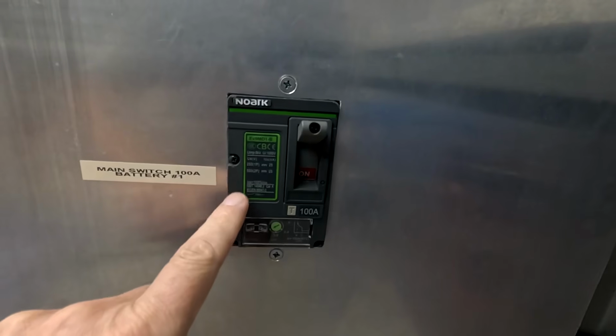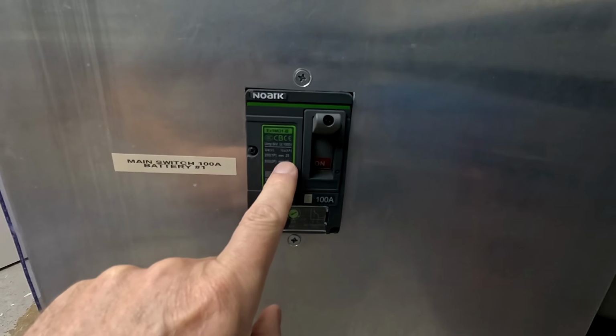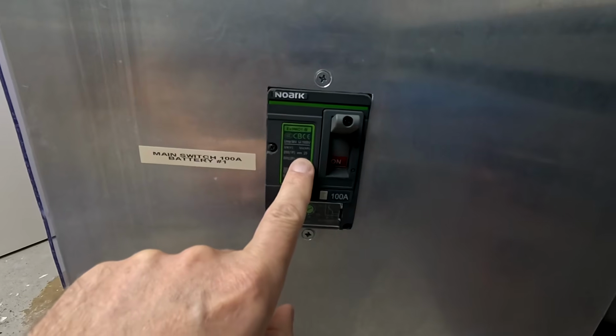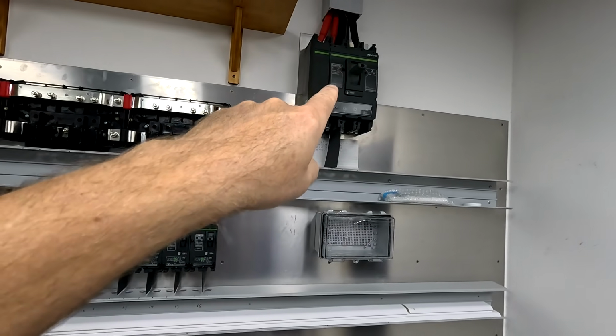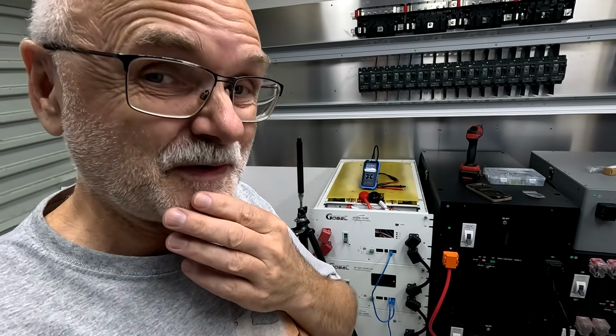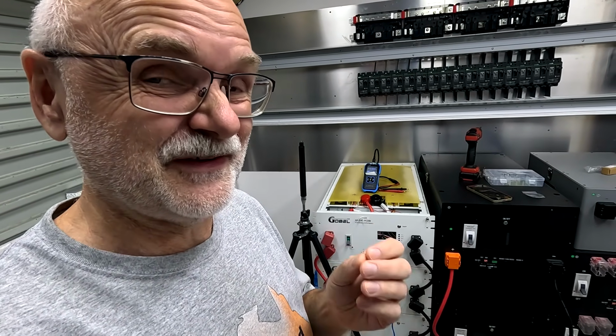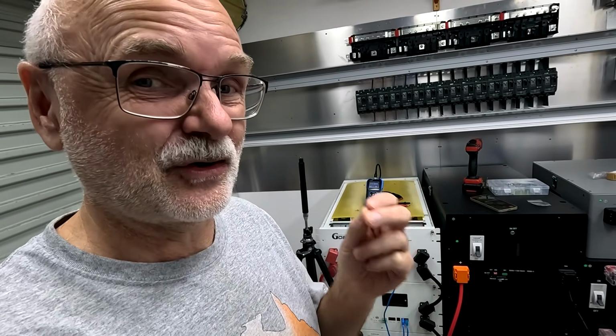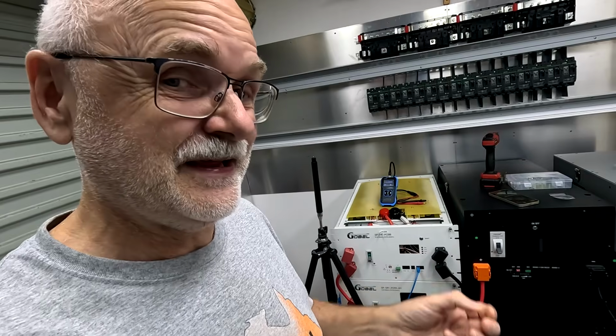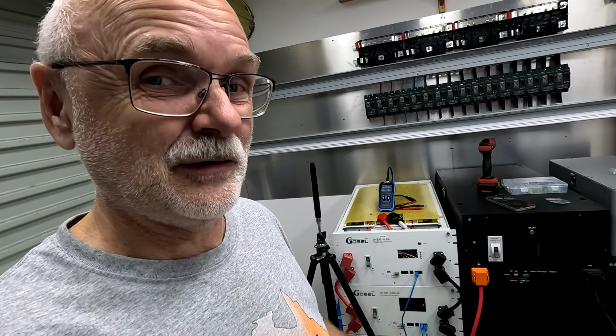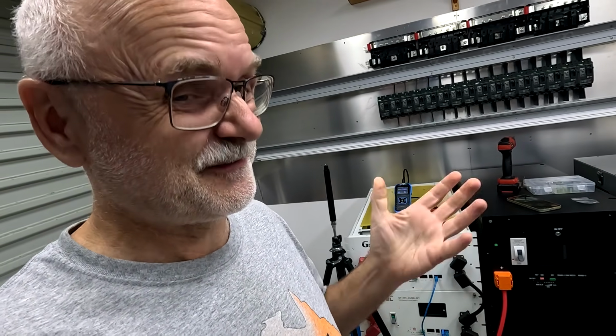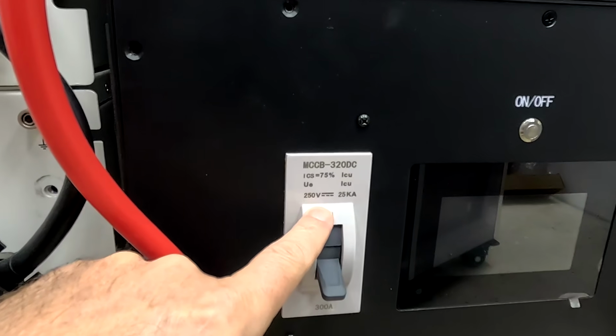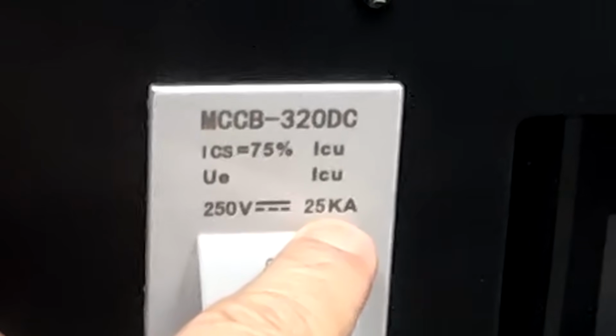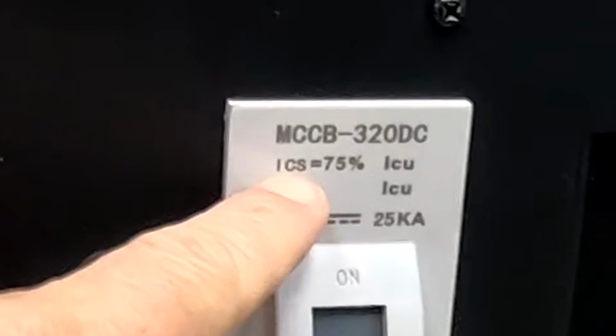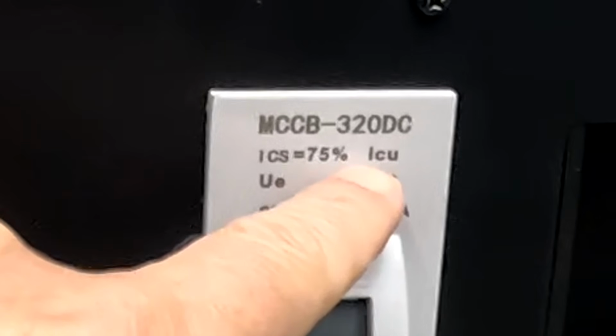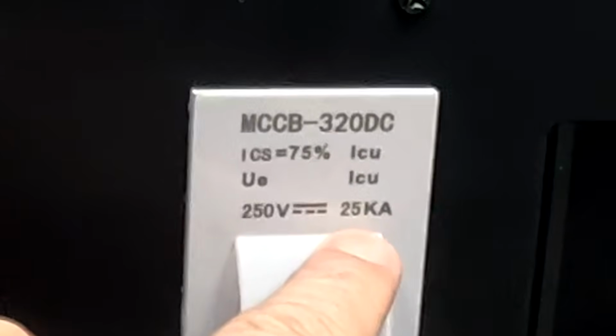50 kiloamps. And this is why I've chosen these breakers here, because they've got 25 kiloamps, 70 kiloamps of breaking capacity. And that's why I'm always saying, I don't think a Class T fuse is actually the solution, only if it has the correct breaking capacity. Usually T-Class fuses can only break 20 kiloamps safely, and with the MB56, you are exceeding this. These ones are the right breakers, 25 kiloamps of breaking capacity, but the ICS is only 75% of the ICU of this 25 kiloamps.